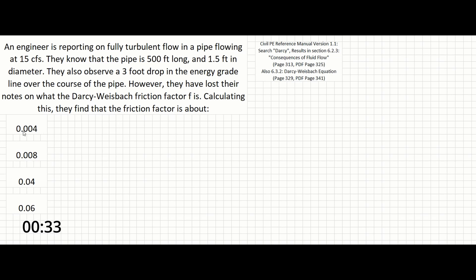We are solving for the Darcy-Weisbach friction factor. The first thing to do is use our reference manual and search for Darcy. This brings you to page 313, where we can get the equation: HF equals F times L over D times V squared over 2G, where HF is the head loss in feet, F is the Darcy-Weisbach friction factor, L is the pipe length, D is pipe diameter, V is the velocity, and G is gravity.